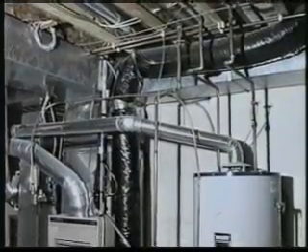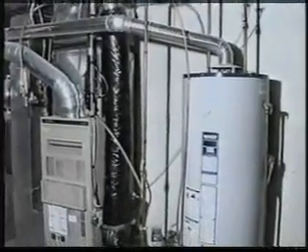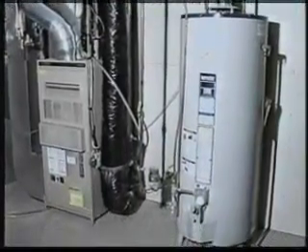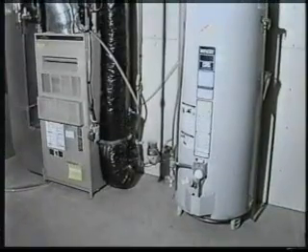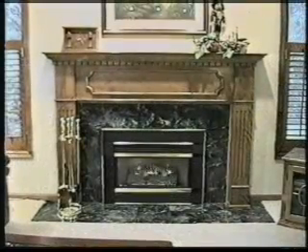Some effects of negative pressure in a modern house include combustion appliances like a furnace, boiler, or water heater starving for air. Backdrafting of air down the chimney creates the potential for carbon monoxide poisoning. Cold air drafting through windows causes condensation and rot on window panes.